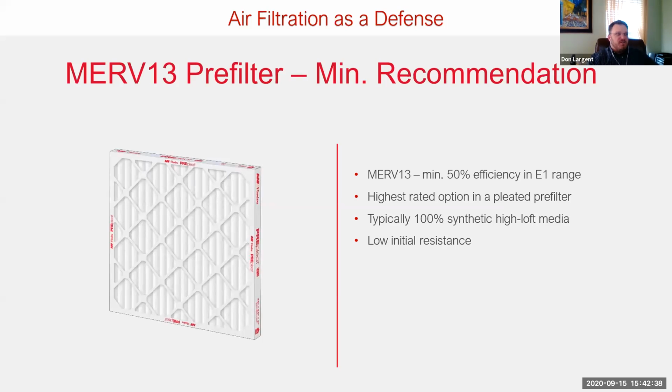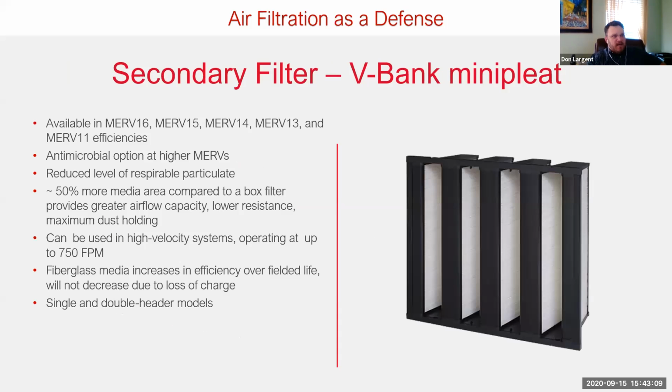From a filtration solution perspective, you've got a MERV 13 filter, which is the minimum recommended, and it's going to give you your lowest initial resistance. But the caution here is that typically those MERV 13 filters are usually 100% synthetic, high loft. When it's 100% synthetic, typically that means it's a charged media. It may lose charge over time, reducing its filtration effectiveness. And as was mentioned earlier, because it's a synthetic, it's usually going to be susceptible to UV light exposure. So keep that in mind.